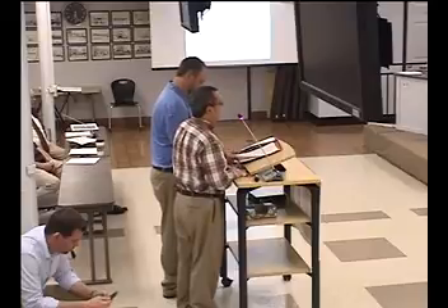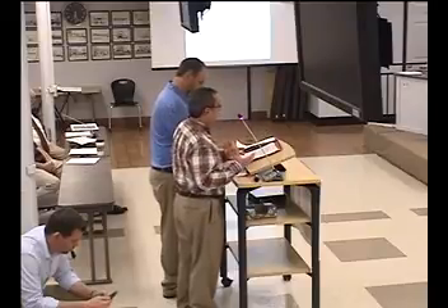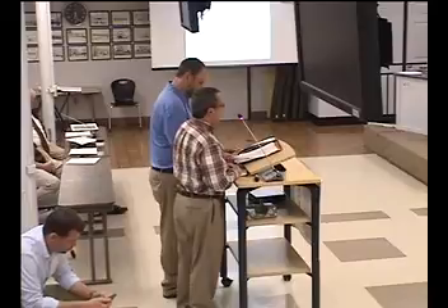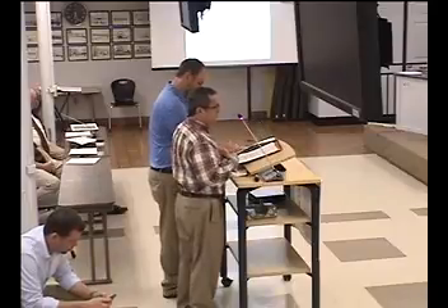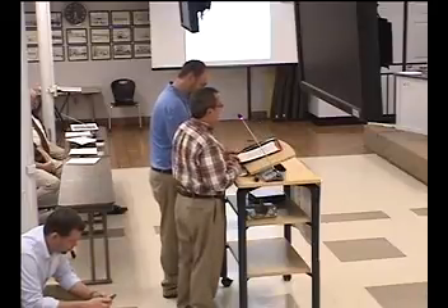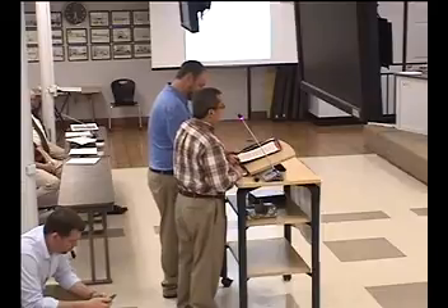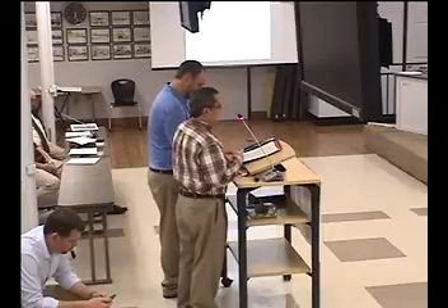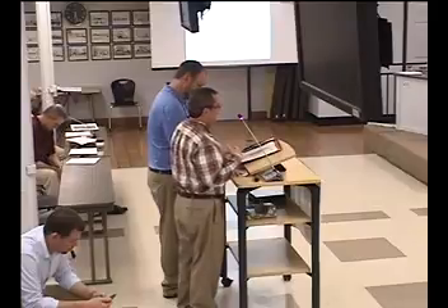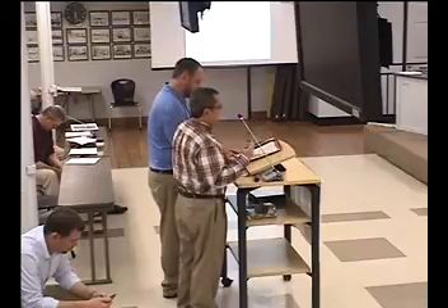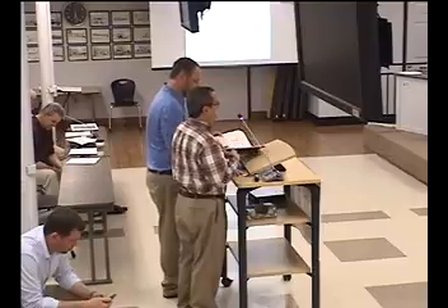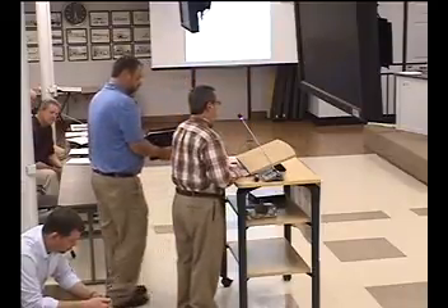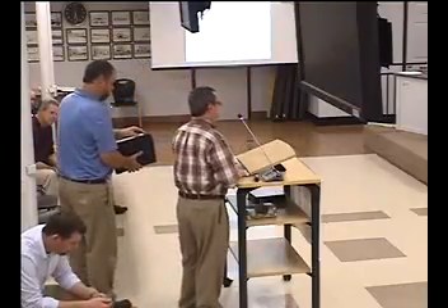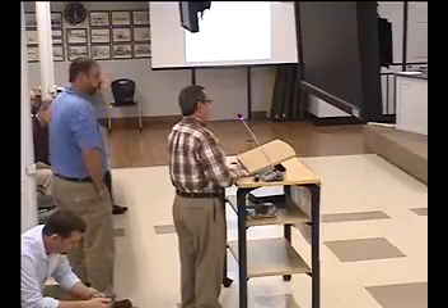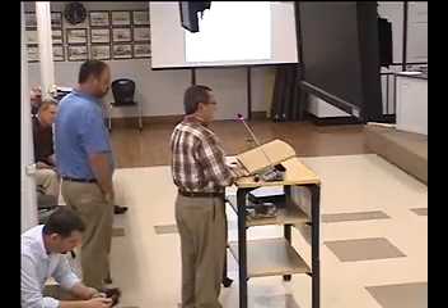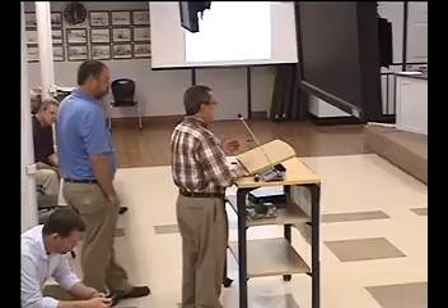The attempts to clean that loop online, if you will, were not aggressive enough. And to John's point, we need to get that stuff out of there so we quit having plugged up heat exchangers, et cetera. So what's happened is we've hired a company that specializes in this. We've installed their side stream filtration unit with the help of Murray County Schools maintenance folks. And it's estimated to take 3 to 6 months to clean the loop up completely.